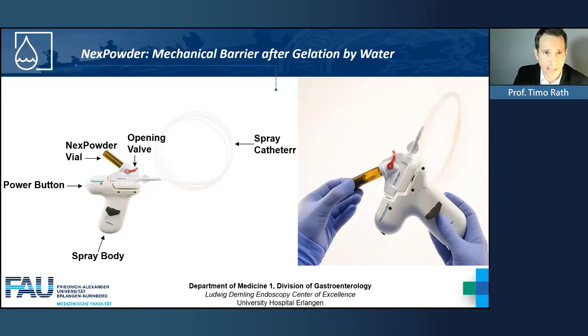So with this airflow through the catheter, but the valve closed, you want to insert the catheter through the working channel. That way you ensure that the catheter, which is flowed with air constantly, and the working channel remain dry. And when you then reach the target tissue and have the catheter advance 2 to 3 centimeters out of your distal scope end, then you want to slowly open the valve to release the powder. That way you prevent actually clotting of the active substance of NexPowder in your working channel or in the catheter. And what happens when NexPowder comes into contact with blood or water is, you see that on the small video here in the upper right quarter, it instantaneously turns into a gel formation.